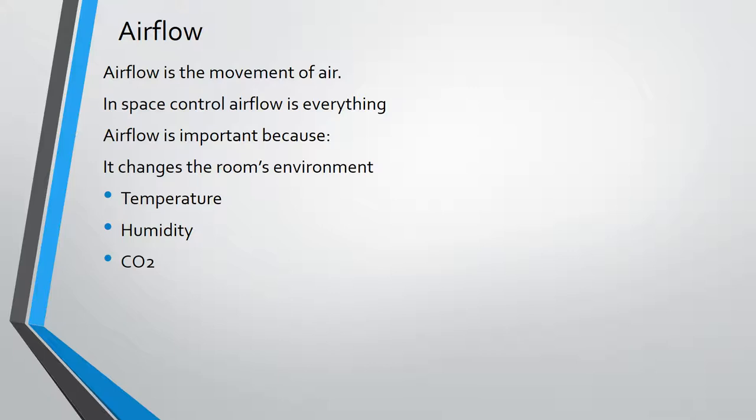So in space control, as I've said, airflow is everything. And it's important because it changes the environment of the room. Temperature, humidity, CO2, all of these things are important, but none of them can be changed without airflow. For example, temperature. If you need to change the temperature, you can introduce cold or hot air. If you need to adjust the humidity, you can introduce air that's more humid or less humid. And CO2, that's all airflow. That's about bringing in more fresh outdoor air to reduce the volume of CO2 in a space.